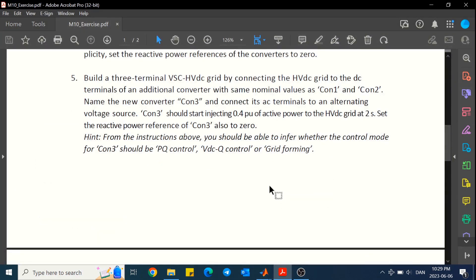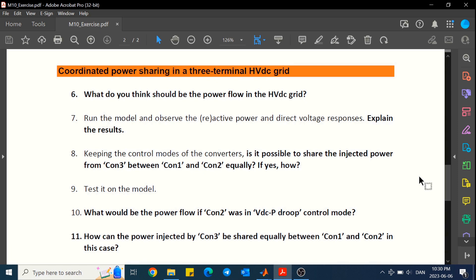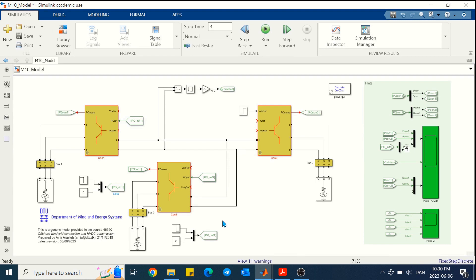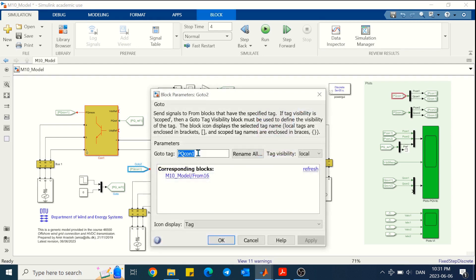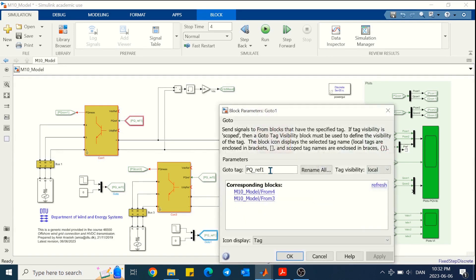It is asked what would be the power flow of converters in the HVDC grid. We expect that converter 2 is absorbing all of the power injected because converter 1 is in PQ control for active power and is injecting power to DC link, and converter 2 is reacting to that. When converter 3 is also injecting some power to DC link, converter 2 does exactly the same and extracts this power from the DC link to maintain the DC link voltage. Before running the model we just need to rename the signals for converter 3. We don't need to change the control mode since it is also in PQ control mode.